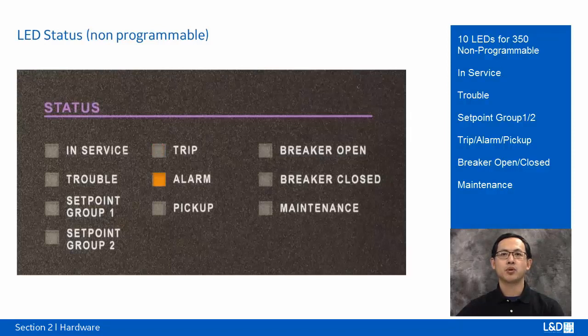Alarm LED will flash in orange color upon detecting an alarm condition, with element function selected as alarm. The LED will automatically turn off if the alarm condition clears. The LED will remain steady on if the function of the operated element is selected as latched alarm.